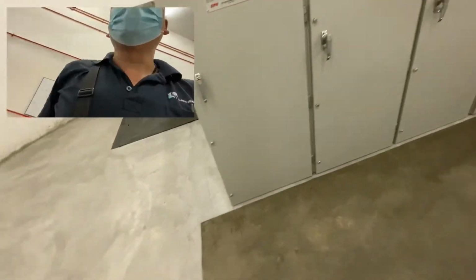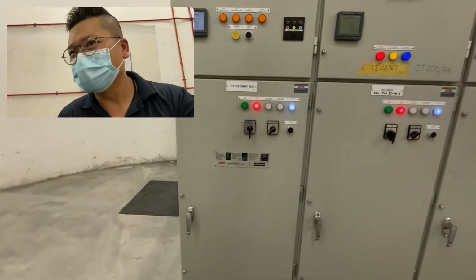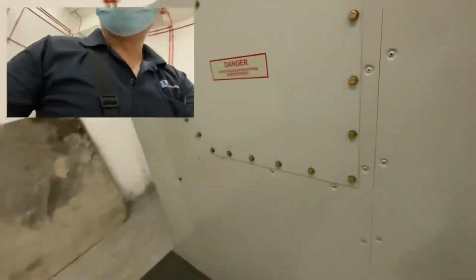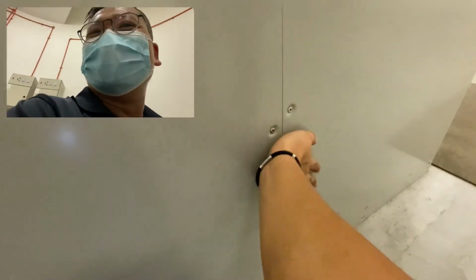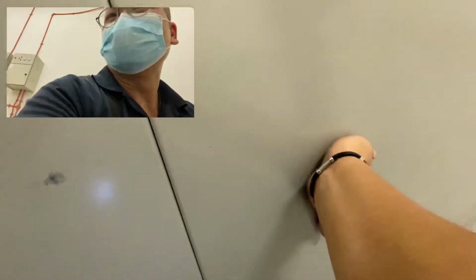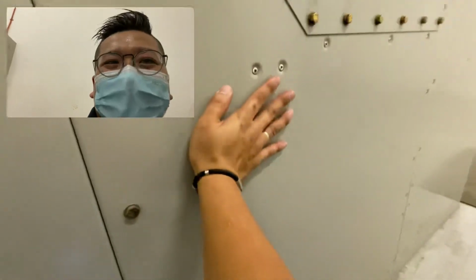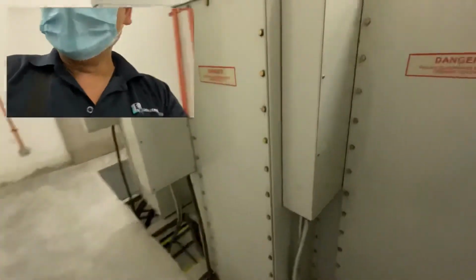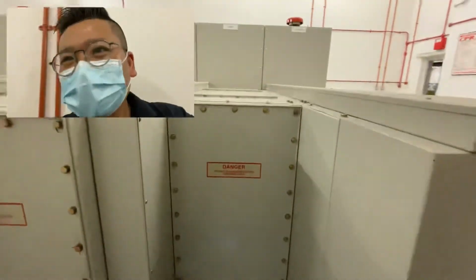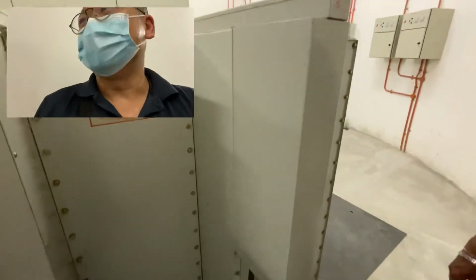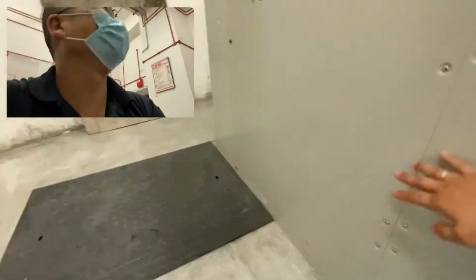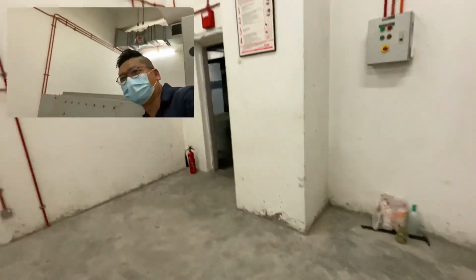Another way to check it: if this is the switchgear and you know the location where the heater is installed, you can feel it here. Here they got two. One is here. You see here is warm. Correct, this is the location of the heater. And another one is here, somewhere around here, but this one a bit center. But at the center of the panel, you can't feel it because you cannot touch that area. So you must use another method. But if some site only has one or two switchgear, then you can check the heater by feeling the heat. It's actually more accurate because you know it's warm, right? Another way, if you have a thermal scan, you can sense the different temperature here.